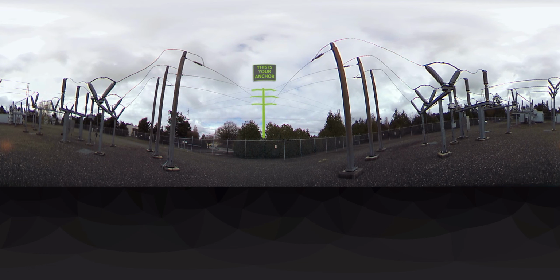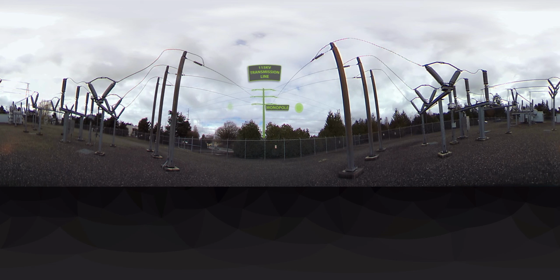Wherever you are at the moment, navigate back to that anchor point, highlighted in bright green for your reference. The first thing of note in this substation is the anchor point itself. It consists of 115 kV transmission lines on the monopole. The lines coming in from the left and right are attached to the same pole, but represent two separate circuits. We'll focus on the circuit on the right.